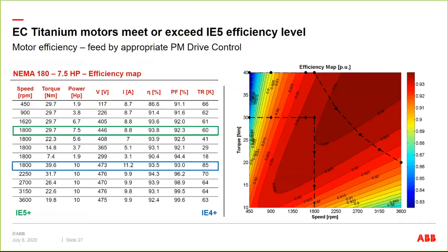This is just kind of a new concept that I want to discuss. I am going to be coming back later this year and doing more of a technology webinar on just this concept, which is what we call efficiency islands. And it's really about matching the system curve for the pump, fan, or compressor in and around an efficiency island operation point. So again, remember I said you can run above base speed.